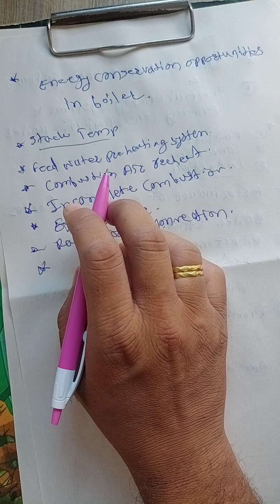Next, automatic blowdown control. Uncontrolled continuous blowdown is very wasteful. Automatic blowdown control can be installed that senses and responds to the boiler water conductivity.